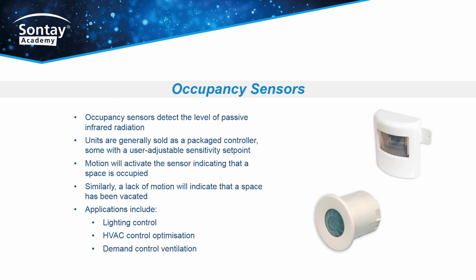Occupancy sensors. Occupancy sensors detect the level of passive infrared radiation. Units are generally sold as a package controller, some with a user-adjustable sensitivity set point. Motion will activate the sensor, indicating that a space is occupied. Similarly, a lack of motion will indicate that a space has been vacated. Applications include lighting control, HVAC control optimization, and demand control ventilation. Occupancy sensing offers many possibilities for the reduction of energy use.